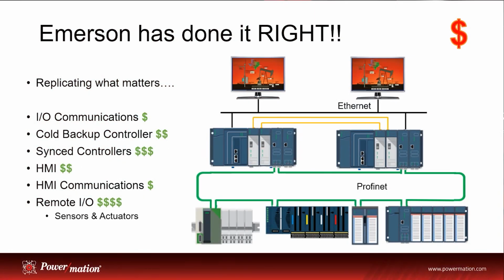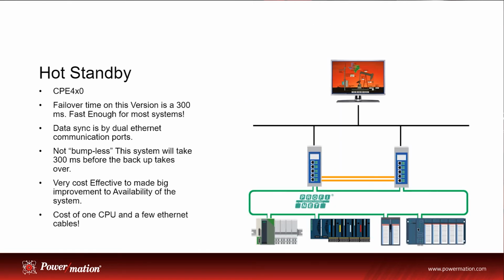Yep. So in the terminology that we work with, we've got what we call a system that's hot standby. And what we mean by hot standby is you can bump. You can say, okay, run for a while. Maybe it's doing RO, maybe it's doing a plastic injection molding system. You're okay to have a half a second downtime while it switches over to the other controller. But there are situations where you need it to be scanned very, very quickly. If you're doing very time-sensitive things, you want the scans to be exactly synchronized.